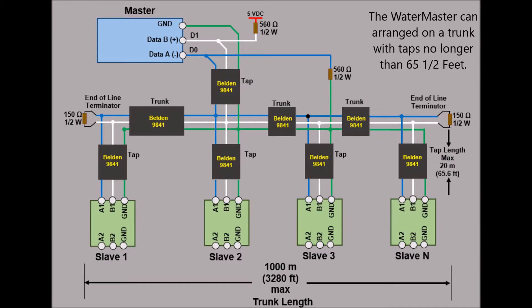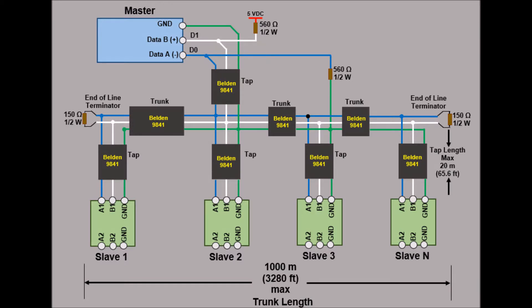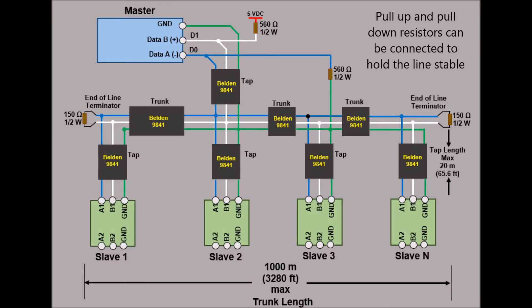The Watermaster can be arranged on a trunk with taps no longer than 65.6 feet. When there is no data activity on an RS-485 balanced pair, the lines are not driven and are thus susceptible to external noise or interference. To ensure the receiver stays in a constant state when no data signal is present, the signal lines need to be biased from a single point on the bus at or close to the master.